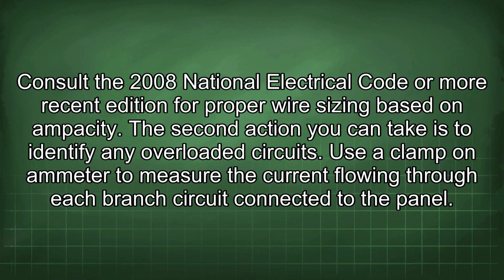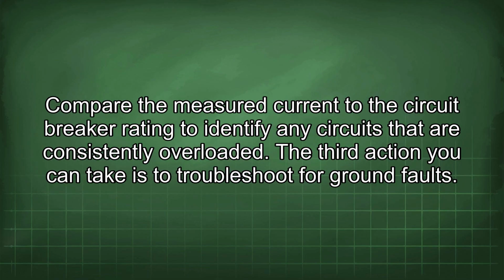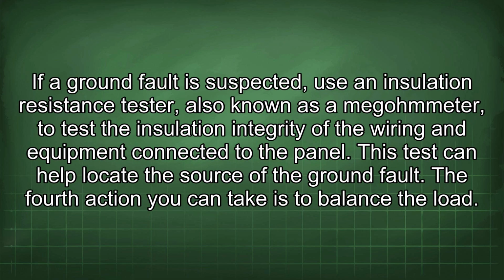The second action you can take is to identify any overloaded circuits. Use a clamp-on ammeter to measure the current flowing through each branch circuit connected to the panel. Compare the measured current to the circuit breaker rating to identify any circuits that are consistently overloaded. The third action you can take is to troubleshoot for ground faults. If a ground fault is suspected, use an insulation resistance tester, also known as a megohmmeter, to test the insulation integrity of the wiring and equipment connected to the panel. This test can help locate the source of the ground fault.